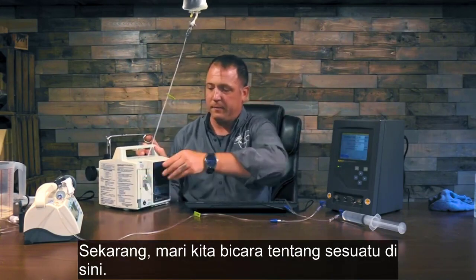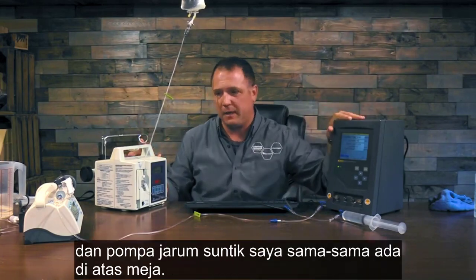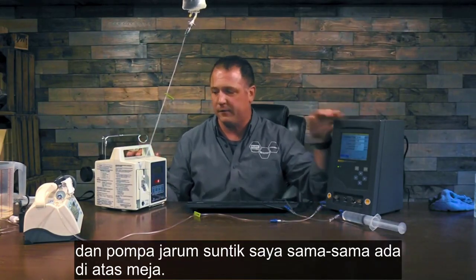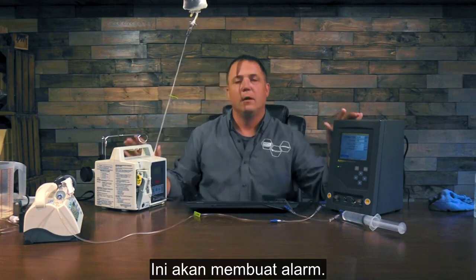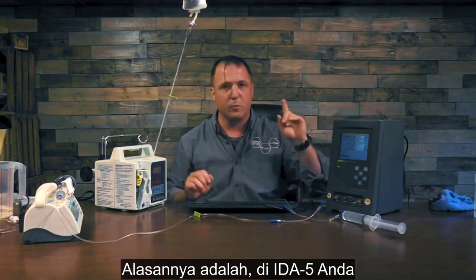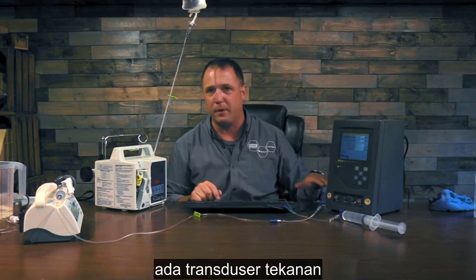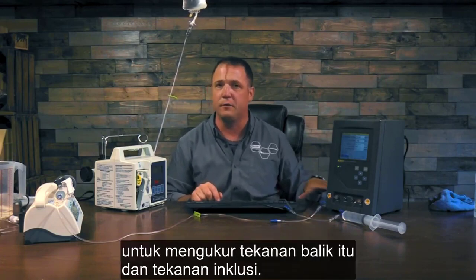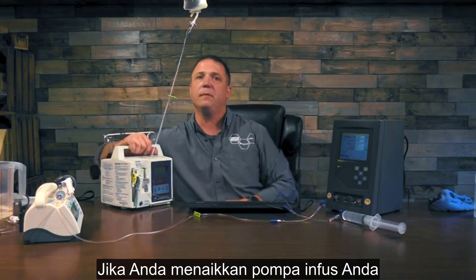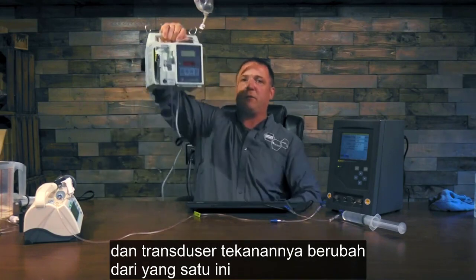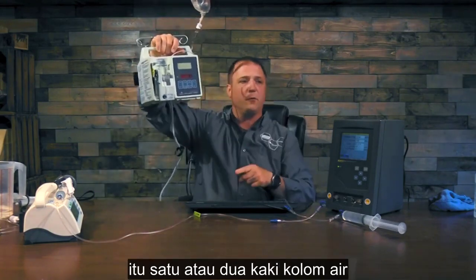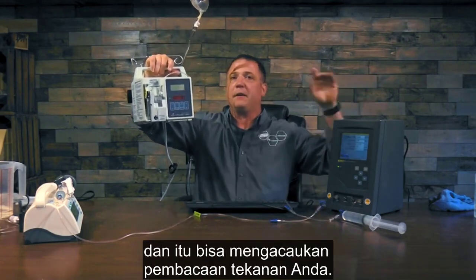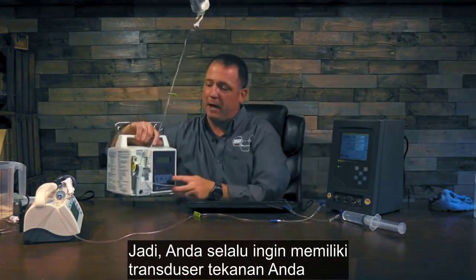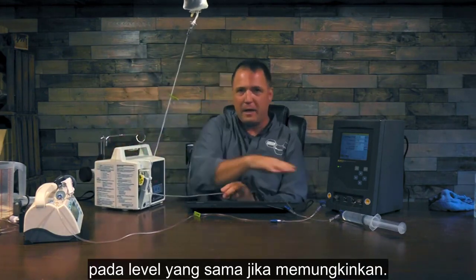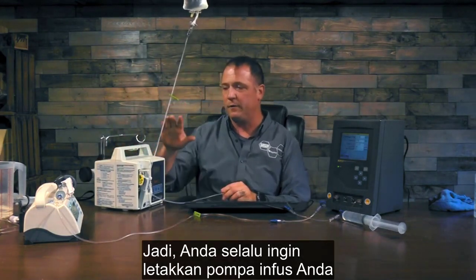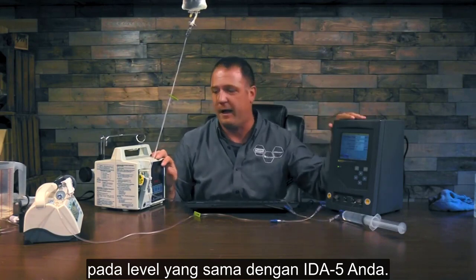Now, let's talk about something here. You'll notice that my IDA-5 and my syringe pump are both on the desk. It's going to alarm at me. Both on the desk on a level playing field. The reason is in your IDA-5 there's a pressure transducer to measure that back pressure and occlusion pressure. If you raise your infusion pump up and the pressure transducer from this one's sitting a foot or 2 higher, that's a foot or 2 of water column that's going to be on your IDA-5, and it can throw off your pressure readings. So you always want to have your pressure transducers on the same level if possible. So you always want to have your infusion pump on the same level as your IDA-5.